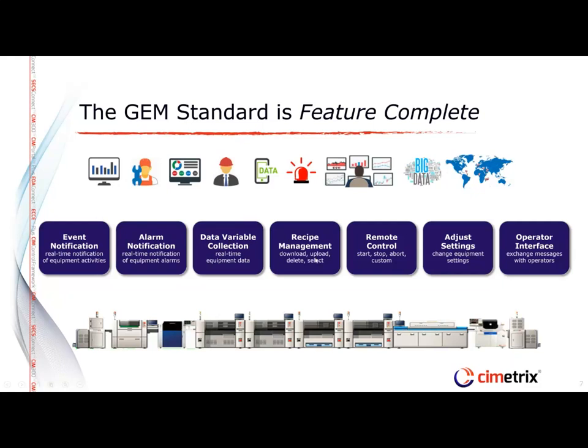There is recipe management for uploading, downloading, deleting, and selecting recipes remotely. There is remote control, which has built-in standardized starting, stopping, and aborting, and it also allows for custom control so each equipment can have custom functionality for whatever needs to be controlled. There are also adjustment settings through the GEM interface, allowing you to tweak equipment behavior for settings that are outside of the recipe.